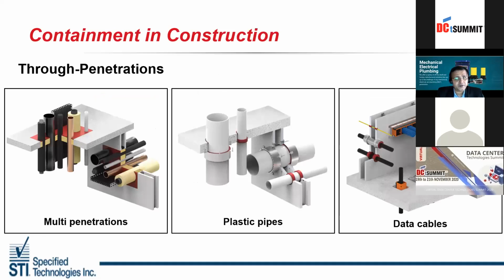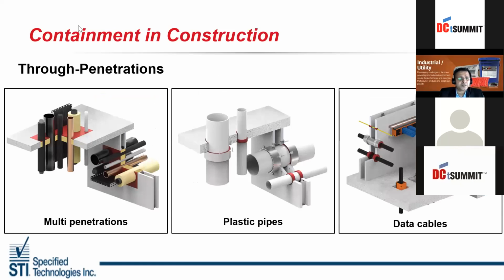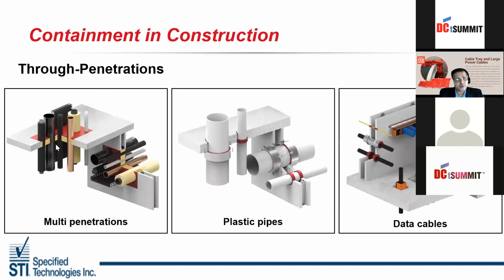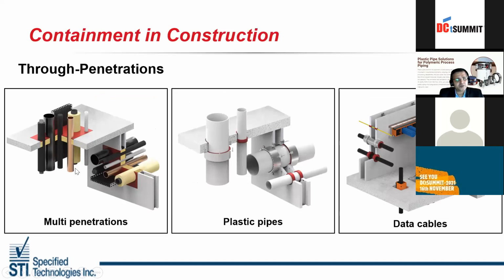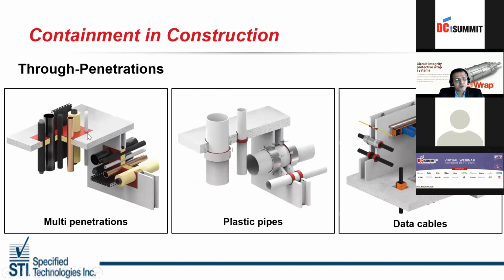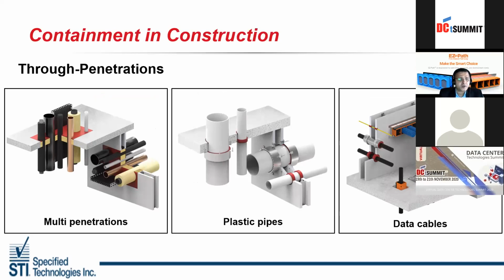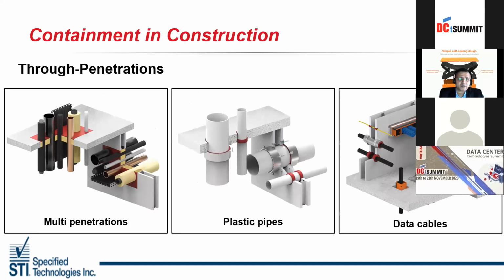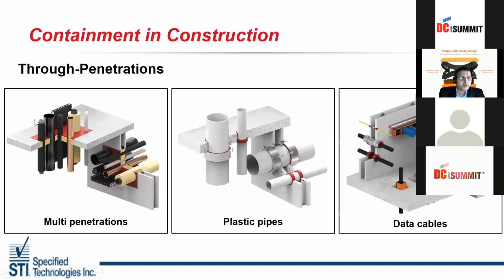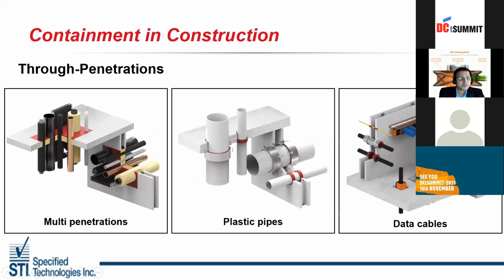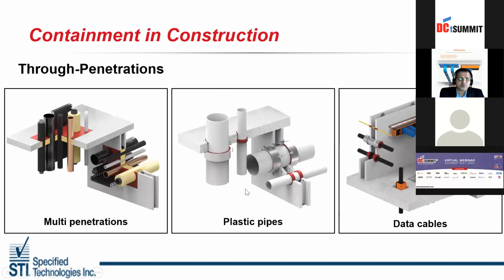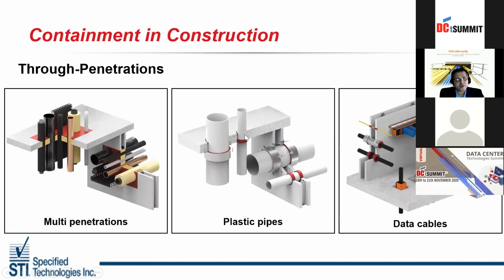Containment in fire systems in a construction, as I mentioned earlier: here I'm trying to show an individual case where you have multiple penetrations passing through the floor or a fire-rated gypsum wall. Towards your left-hand side are the multiple penetrations, where you have insulated pipes, cables, and combustible pipes passing through a wall. So an equal amount of fire-rated, tested system has to be applied in those scenarios. The center one is the combustible pipes. Each combustible pipe, like a 2-inch pipe, can be sealed with an intumescent sealant.